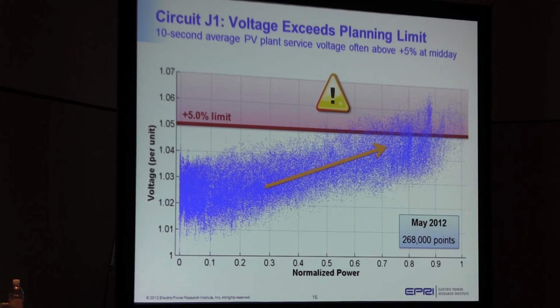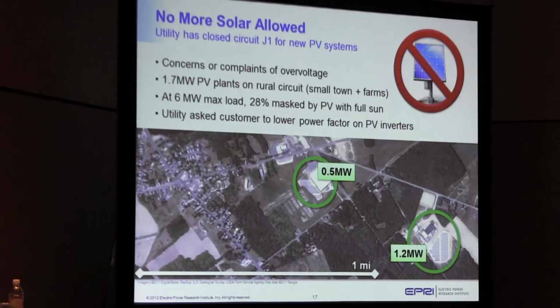In fact, we exceed it quite a bit once we get above 60% of the rated output of the system. So this could actually cause a problem. In fact, it has caused a problem. The utility has closed this circuit, J1, for new PV systems. They said, no more, that's it. There are concerns and complaints of over voltage, and at a 6 megawatt maximum load, 28% of that could be masked by these PV systems. Additionally, the utility has asked the customer of these PV systems to lower the power factor on the inverters.